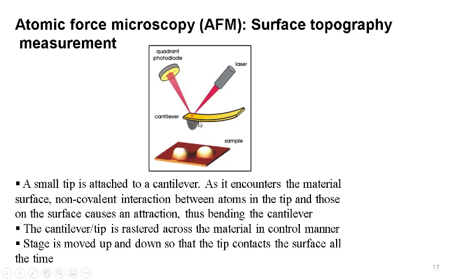AFM can be used in contact mode or non-contact mode. The tip can be made electroconductive to find the electrical conductance map of a surface, or made magnetic for magnetic profiling of the sample. AFM has multiple applications. For soft materials, tapping mode can be used to find the mechanical property of the surface, providing information about micro-mechanics, chemical modification, and functional groups present on a biological material sample.